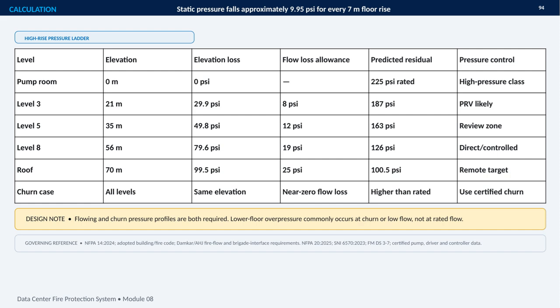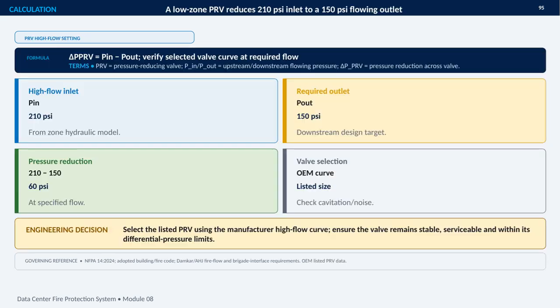Lower floor overpressure commonly appears during churn or very low flow, when friction losses are minimal, so certified churn data is essential. Final decisions should be checked against NFPA 14, NFPA 20, SNI 6570, FM guidance, adopted fire code, and applicable AHJ requirements. This calculation shows how to establish the high flow setting for a low zone pressure reducing valve, or PRV.